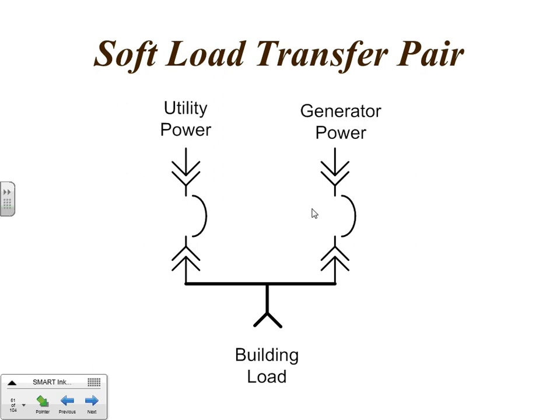The utility breaker opens through power provided by the generator set, then the breaker closes from the generator to the load. When the utility comes back, it's seen by the voltage sensors in the switch, and it starts to synchronize the two sources together. When they come into sync, they're actually looking at the voltage and the frequency. And when both are in sync, this breaker will close and both will be supplying load to the building. And it can stay closed, like I said, for several seconds, and then the generator breaker will be forced open and everything is back to normal.